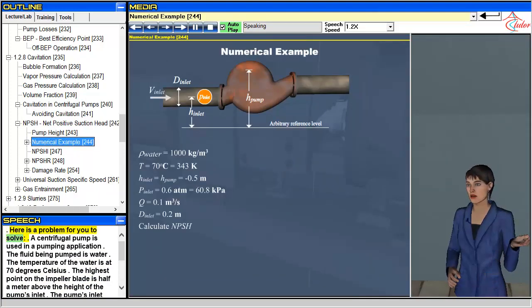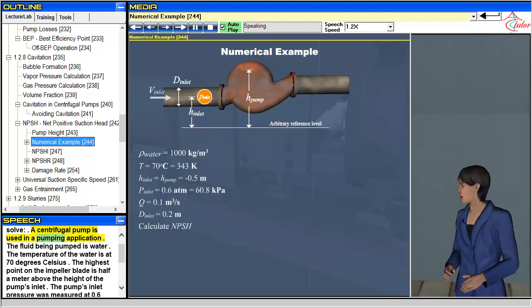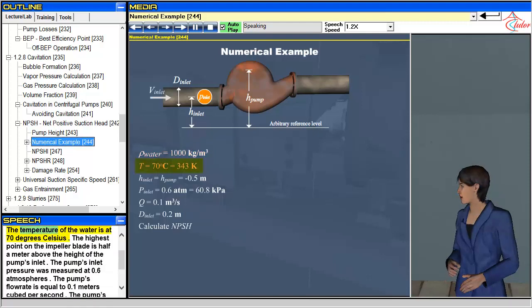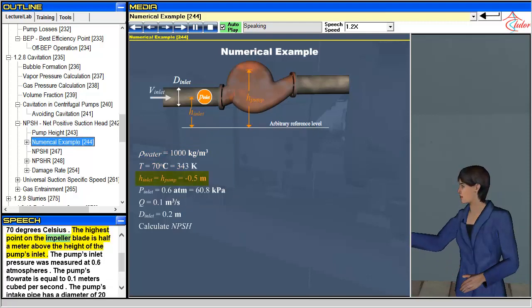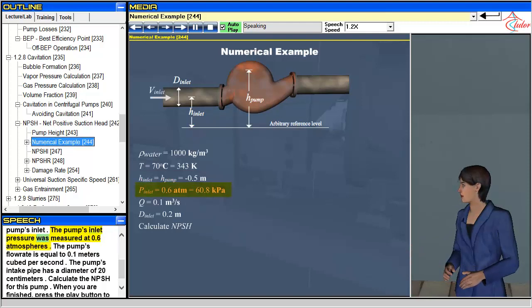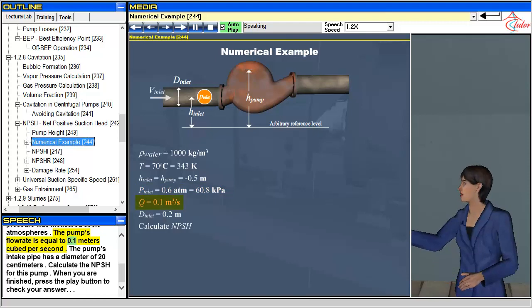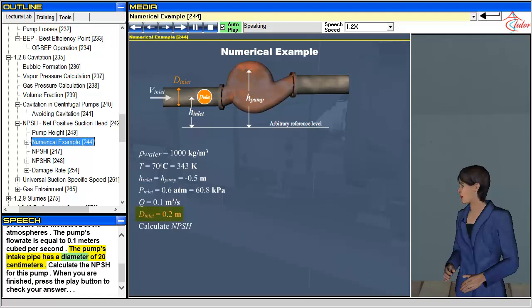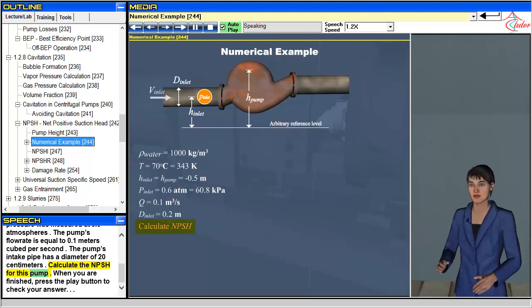Here is a problem for you to solve. A centrifugal pump is used in a pumping application. The fluid being pumped is water at 70 degrees Celsius. The highest point on the impeller blade is half a meter above the height of the pump's inlet. The pump's inlet pressure was measured at 0.6 atmospheres. The pump's flow rate is equal to 0.1 meters cubed per second, and the intake pipe has a diameter of 20 centimeters. Calculate the NPSH for this pump. When you are finished, press the play button to check your answer.